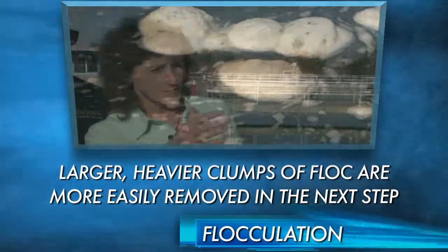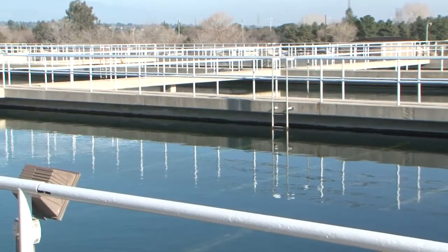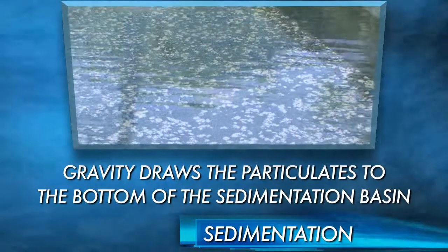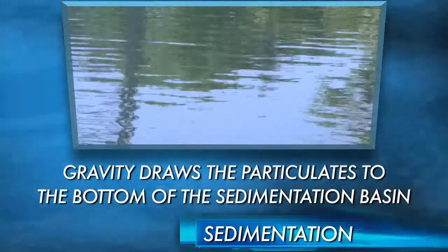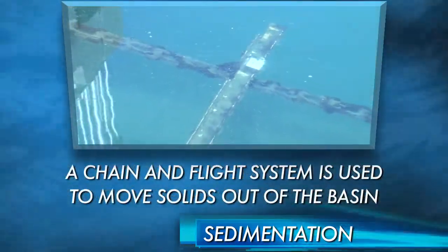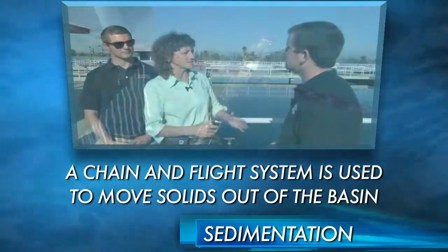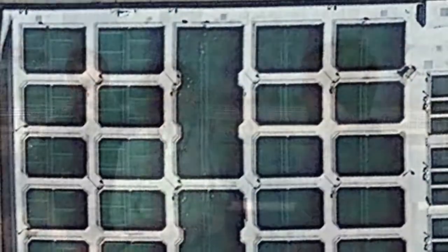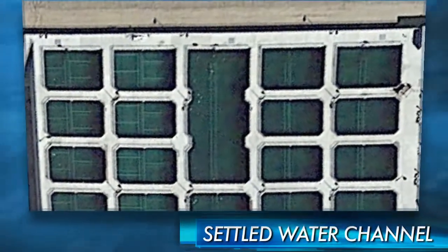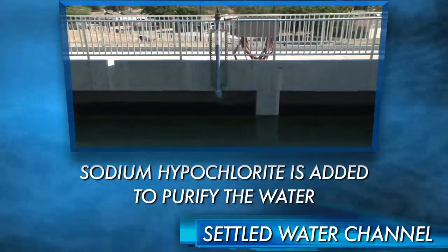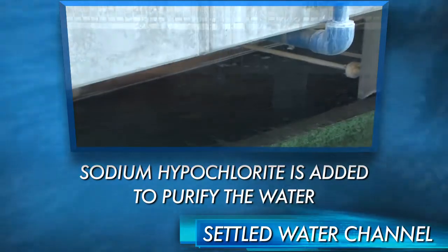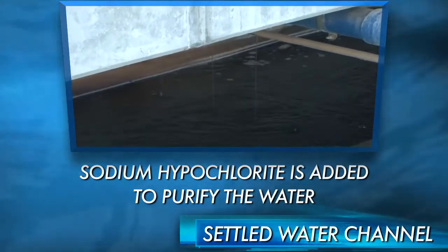After it leaves the flocculation basin, it is then introduced into the sedimentation basin. And the sedimentation basin is where most of the floc particulates settle out, collected with sludge collectors, and that's how they are pulled from the basin to keep the basin from getting plugged up with all the fallen floc. And after the sedimentation basin, we hit the settled water channel. At that point, we introduce our sodium hypochlorite, and that's our primary disinfectant.